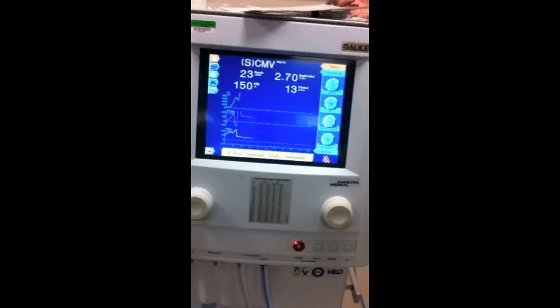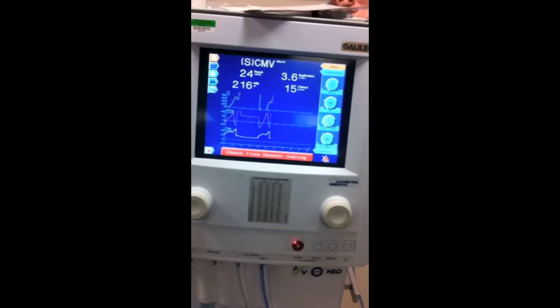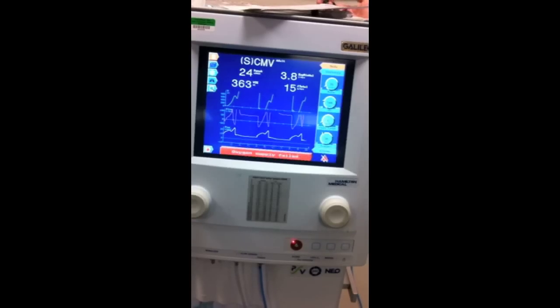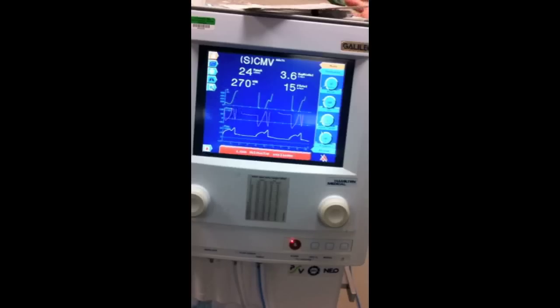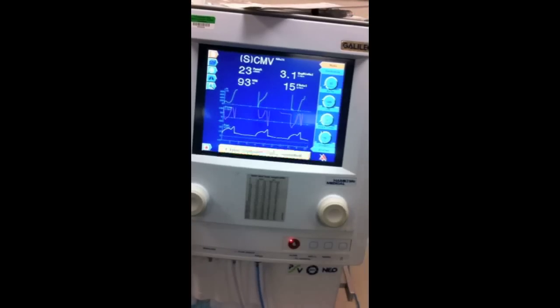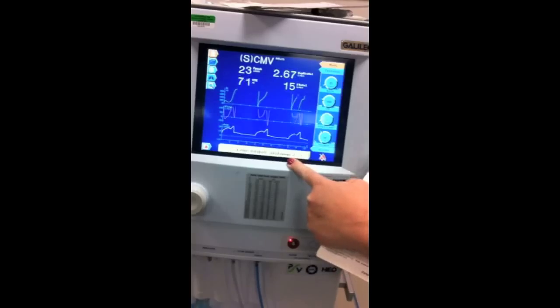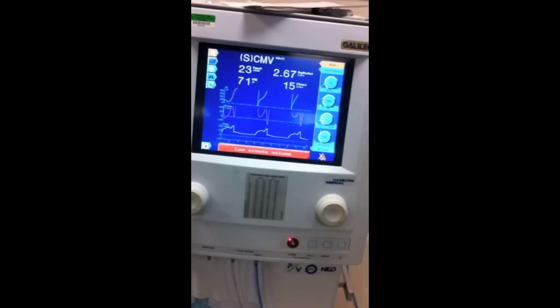You need to do this, because when you do your testing, I'm not going to make you go through every single stage on this pre-operational check, but you need to be able to tell me that this is part of your calibration. In this calibration, there is also the flow sensor test and the tightness test, which I'm going to show you how to do. So here we see our oxygen supply failed. Did you guys see it? So once you get that, you can put it back in.